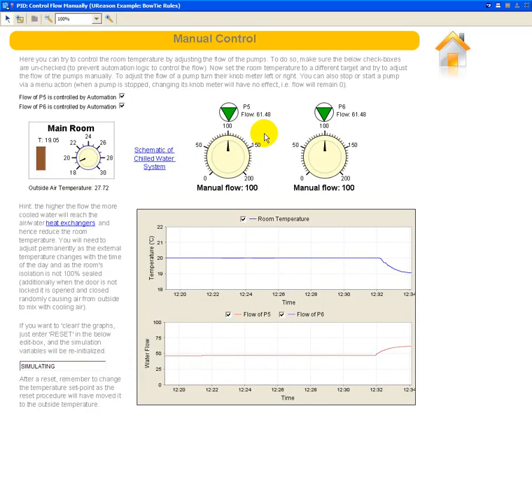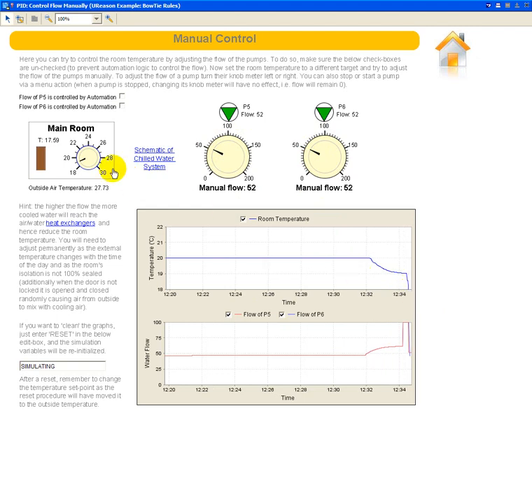We can also try to do this manually. And to do this manually, I have this page here where I can just disarm the control of the flows by the PID and manually control. So now I have set these pumps are running at 100 instead of running around 50 or 60. So they will obviously cool down the temperature of the room. So we don't want that. So we probably want to reduce the flow of these pumps to something around 50 again, and see if that affects the temperature, if we can get back the temperature around the 19 degrees, because that is the value that we wanted here.